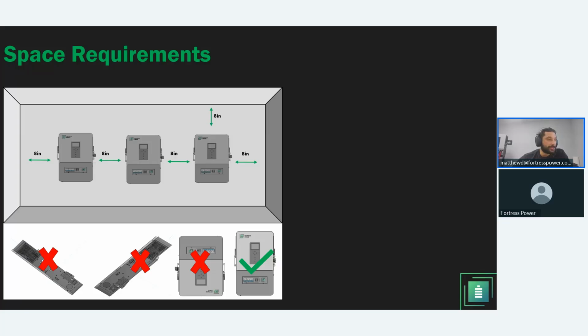The one thing we do want to consider when installing these is that the PV disconnect, which would be this guy right here, is not over 6.7 feet per NEC code, right? You want that to be reachable in order to be disconnected. Do not install it at an angle, right? Always keep it flat against the wall, not upside down, not on the side or anything like that. Okay.